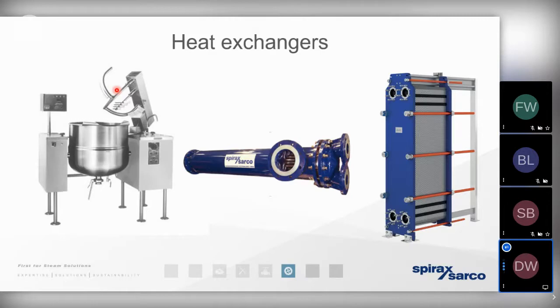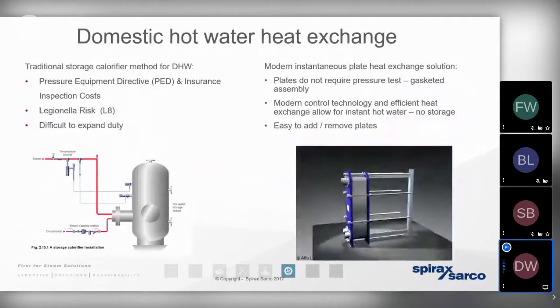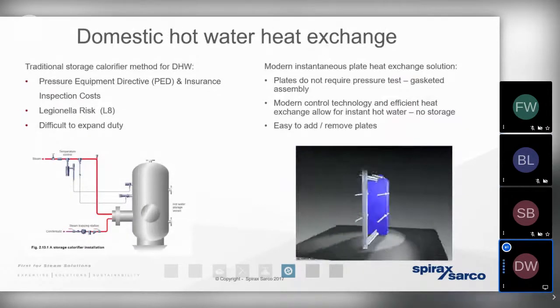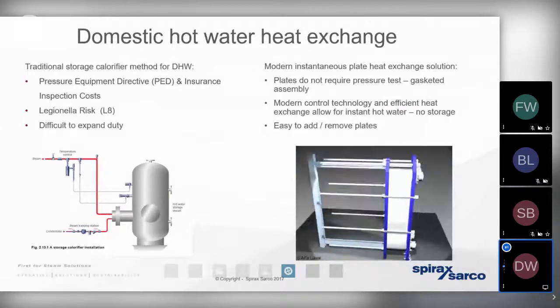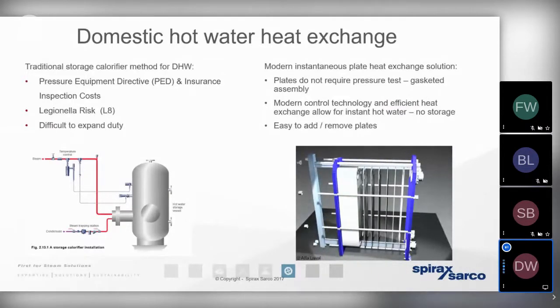But I just want to look now at how shell and tube heat exchangers compare with plate heat exchangers. So shell and tube heat exchangers can be non-storage or flow type, or they can be storage heat exchangers. So let's consider a traditional shell and tube storage heat exchanger, sometimes referred to as a calorifier. And these are still widely used in a lot of building service applications and also a lot of process applications. And that's largely down to the peace of mind that that huge buffer vessel of hot water can provide.